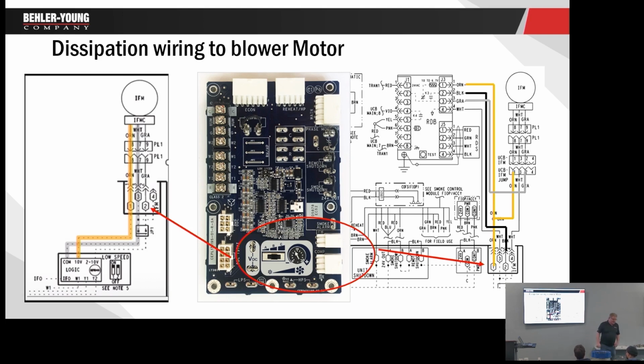Okay, so the good news is if you sat in on the residential training, you had to wire this. You sit in the rooftop unit training, you find out, yay, I don't have to wire this, it's already installed. Your installation is no different. Set it, power, check your transformer, set your static, we're good to go. This is already done. But I want to see where this wires in. Now residentially, we have to wire it in. Here we don't. So these terminals here, remember on our board?